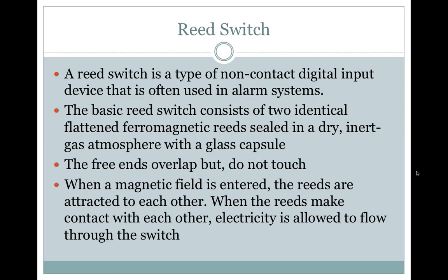Reed switch. A reed switch is a type of non-contact digital input device that is often used in alarm systems. The basic reed switch consists of two identical flattened ferromagnetic reeds sealed in a dry, inert gas atmosphere within a glass capsule. The free ends overlap but do not touch. When a magnetic field is applied, the reeds are attracted to each other, and when they make contact, electricity is allowed to flow through the switch.